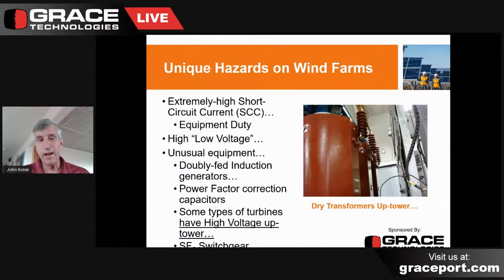Again, they also have very high low voltages in the system. So when we talk about that, I'm understanding now that we have wind generators that are generating at 1500 volts, yet the low voltage windings are just that. They're configured as a low voltage winding, even though they are actually operating at considerably higher voltage than we used to consider low voltage. There's also unusual equipment on wind farms that require training. For example, the doubly fed induction generators. Well, again, calculating short circuit current on those is useful, but better still to get the manufacturer's information from an engineering standpoint.